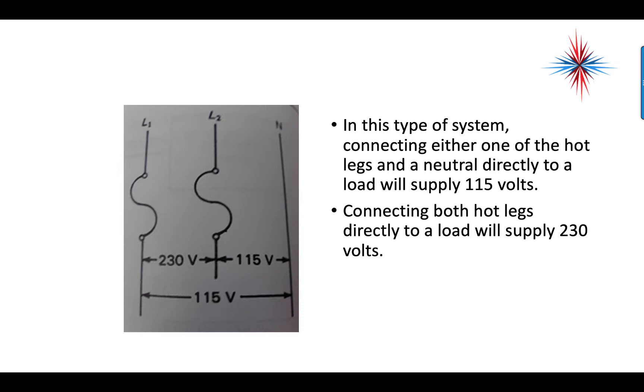In this type of system, connecting either one of the hot legs and neutral directly to the load will supply 115 volts. Connecting both hot legs directly to a load will supply 230 volts. More often than not, a light switch, small appliance, TV, or satellite dish receiver will be at L1 or L2 to neutral. Your cooktops, dryers, air handlers, and condensing units would go L1 to L2 and get 230 volts.